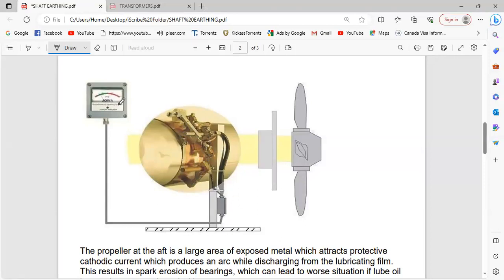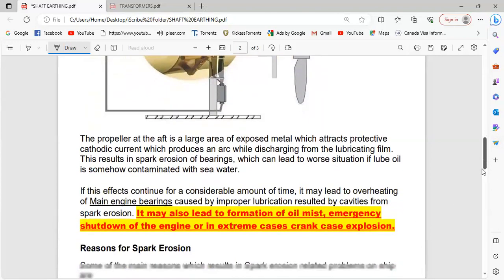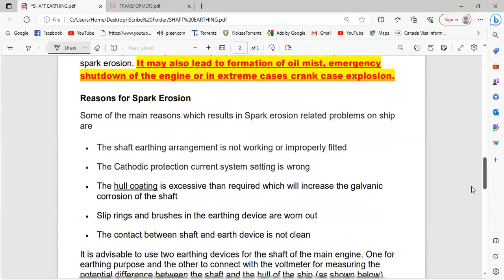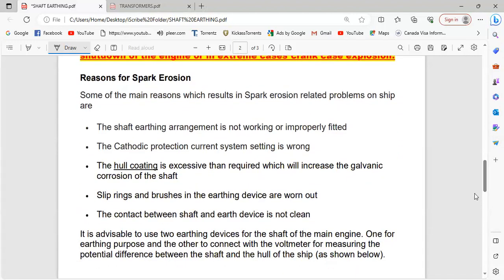This one that is going to the meter has no effect on the system, because it is only giving the ground path for the indication. But of these, at least one of them has to be in circuit at all times. Because if you remove that, the current is going to go down your shaft and damage your main engine bearings. Okay, just that instant is more than enough. Okay, clean this. Okay, we'll see the maintenance now. First we'll take the reasons for the spark erosion, then we'll see the maintenance.